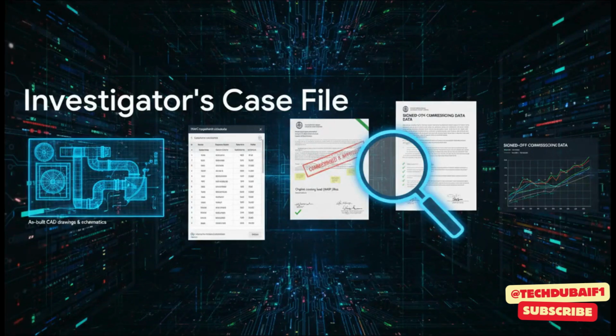And to find that gap, you've got to assemble your case file. We're talking everything: the original CAD drawings, the schedules for all the equipment, and the commissioning data that proves the system actually worked correctly at one point. But most important of all are the real-time data logs from the building's own management system. The first clues are always buried right there in the data.